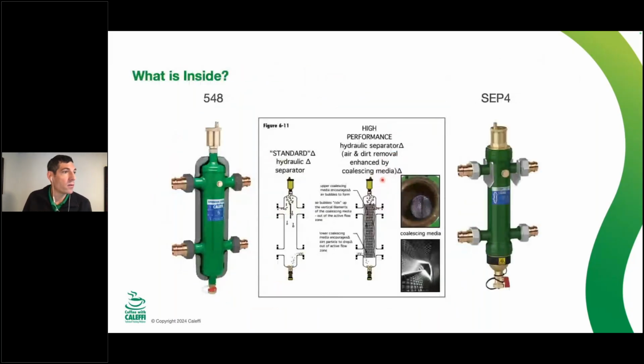Okay, so now inside of a hydro separator, there are a lot of different ways to build these devices. We can have a very simple hydro separator that maybe is just a completely open vessel or has a baffle or something like that. I would call this the minimum device to do primary, secondary piping. This is going to be more cost competitive without some of the high performance features I'll talk about on the right side here. Absolutely will work for primary, secondary piping. Is it high performance air and dirt separation? Not really, and I'll talk about that more as we get closer to the end of the presentation.